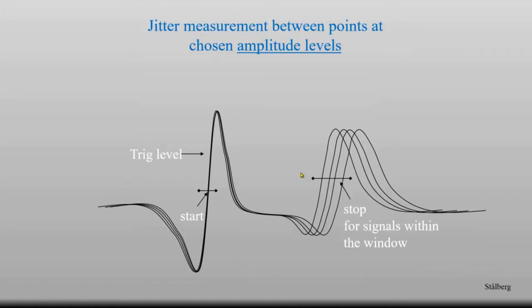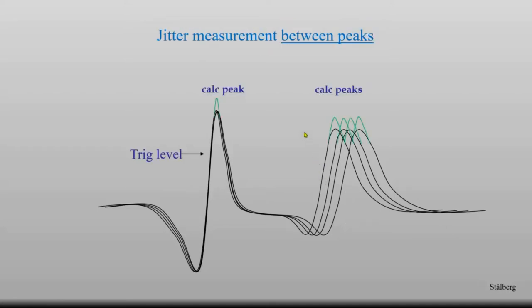To quantitate this we need to measure the time between the first and the second pulse. The original method used time windows: a starting point and then like a stopwatch, the measurement stops when the signal passes through the window. This technique is still used in some equipment. Another possibility is to measure between the peaks — between this peak and this peak — and for a simple signal, it gives exactly the same jitter value.